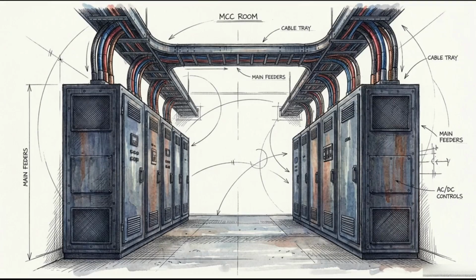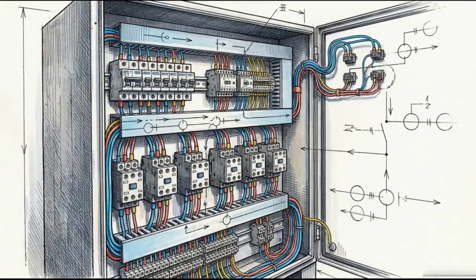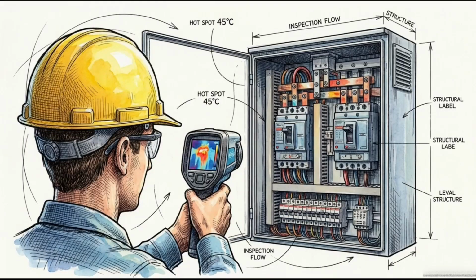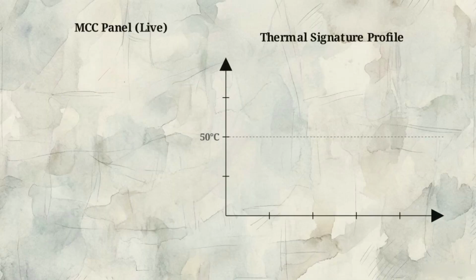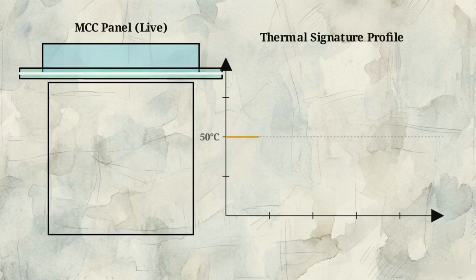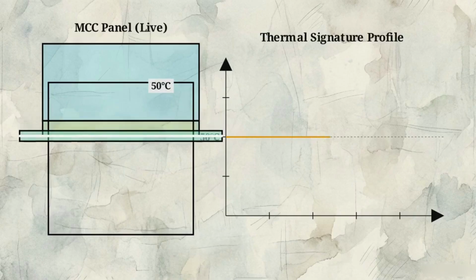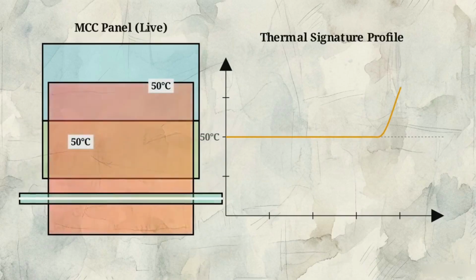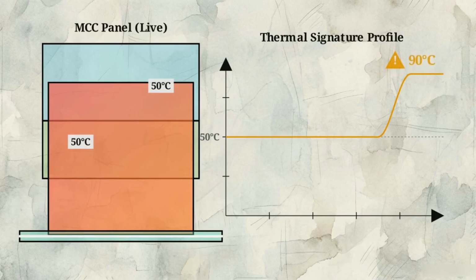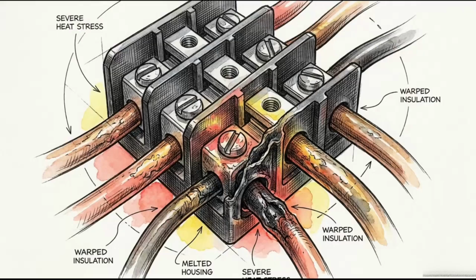Beyond the macrogrid architecture lies the operational heart of the factory, the Motor Control Center, or MCC. This is where power is actively switched, routed, and monitored. In this environment, engineers employ predictive diagnostics to identify physical degradation before a breaker trips or a fire breaks out. Thermography lets us audit energized panels without stopping production. Normally, drives and terminal blocks sit at a steady, ambient 50 degrees Celsius. However, oxidized connections create localized resistance. This generates heat, manifesting as a thermal spike reaching 90 degrees or more.